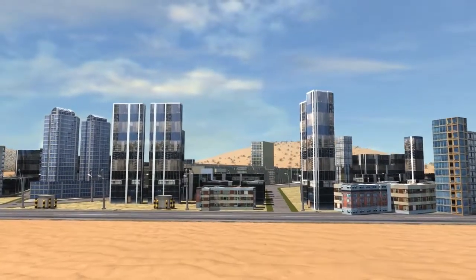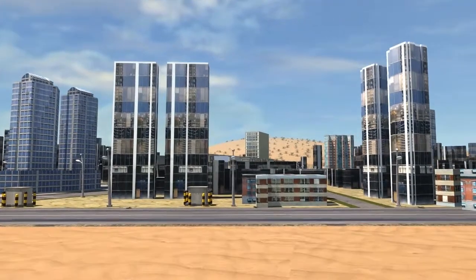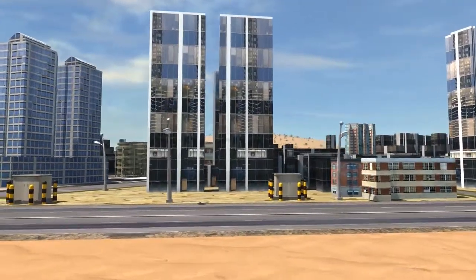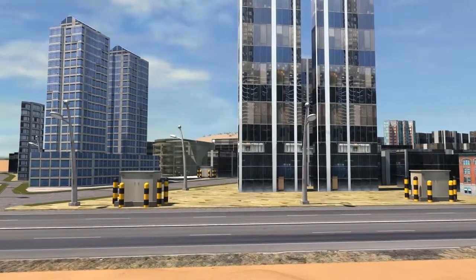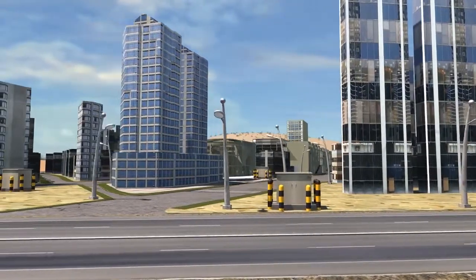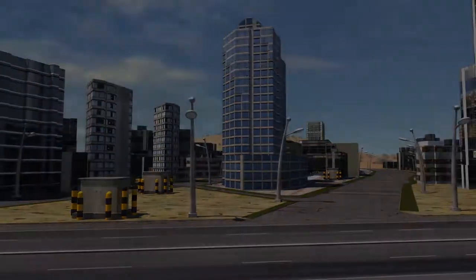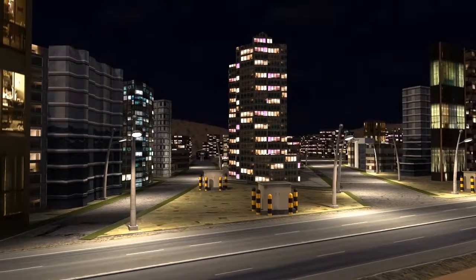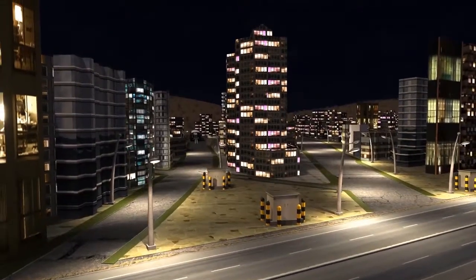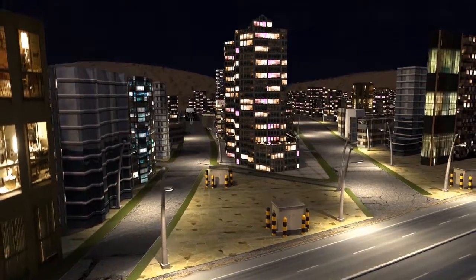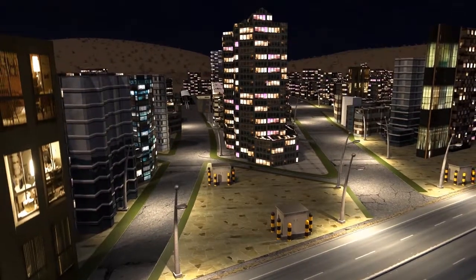Residential customers are supplied from the distribution network substations. The substation has a transformer which converts the 13.8 kV to low voltages of 127 volt or 220 volt. The low voltage is distributed from the low voltage panel. Finally, the low voltage is delivered to the customer by using a mini pillar, so customers receive a supply of electrical power required by them at the time and place at which they can use it.